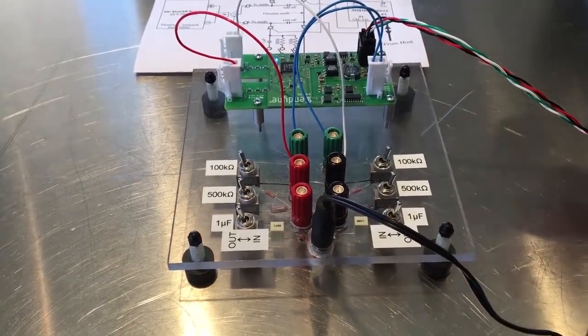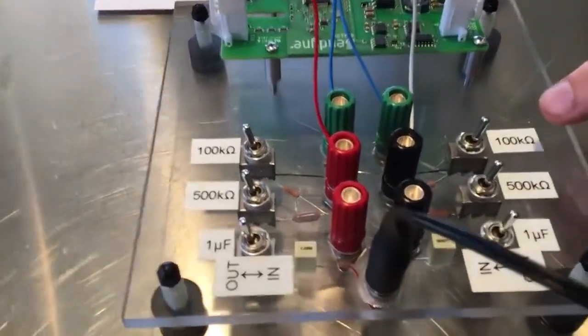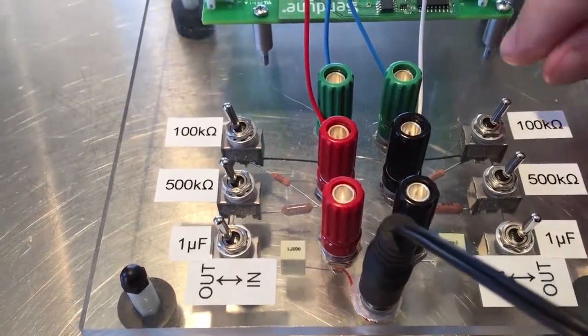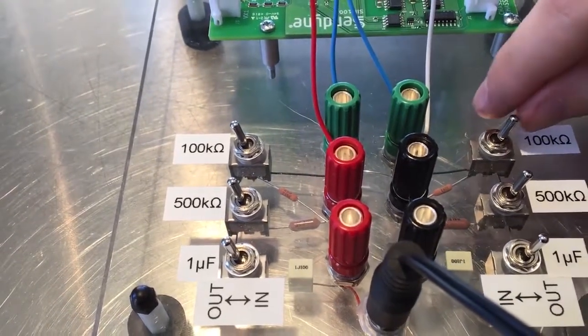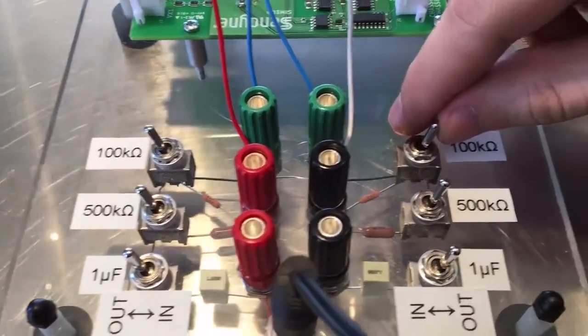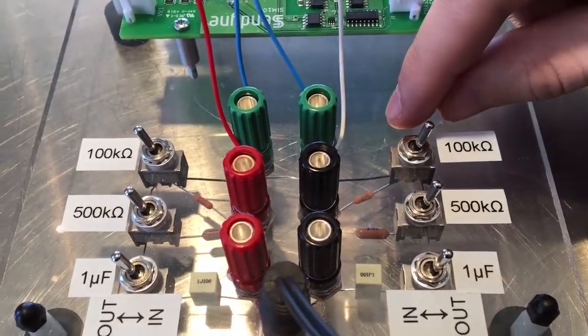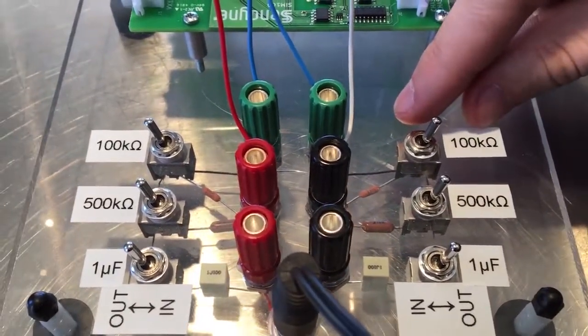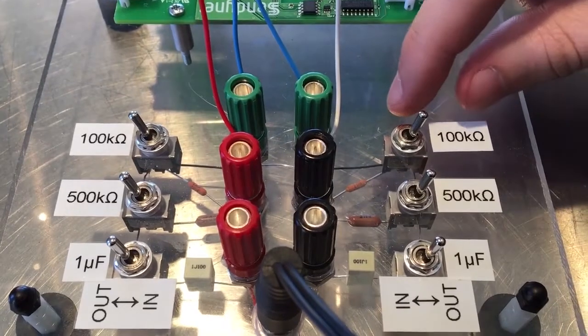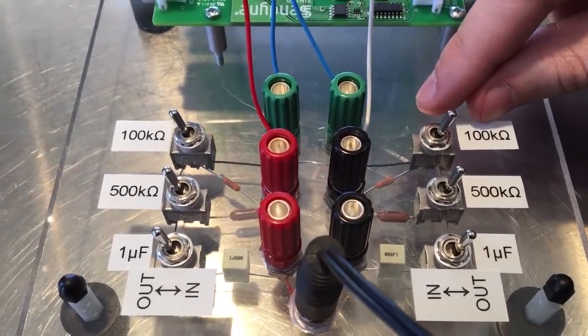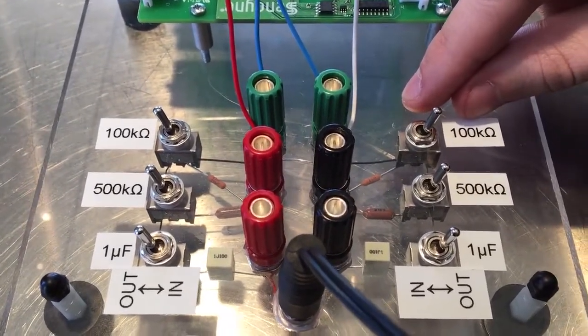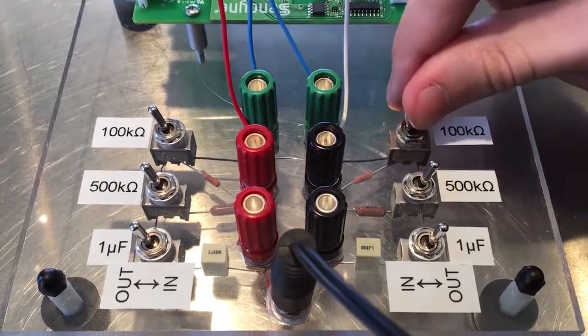Now I will be introducing 100 kiloohms of leakage resistance on the negative side of the battery. When I flick the switch towards the binding post, that means that the 100 kiloohms of leakage resistance is added in parallel with the resistance of the board.